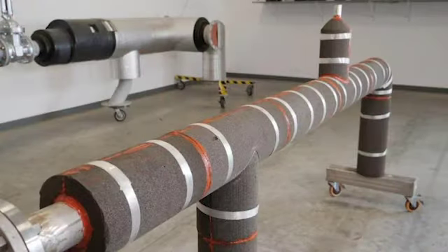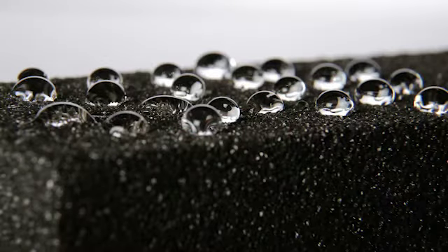And the foam glass sealed system addresses this. Can you explain to us how it works? Absolutely. The basis of our foam glass sealed system is our FOAMGLAS One cellular glass insulation. This is a closed cell, rigid, non-absorbent material with a water vapor permeability rating of 0. This insulation acts as its own vapor barrier against moisture ingress.